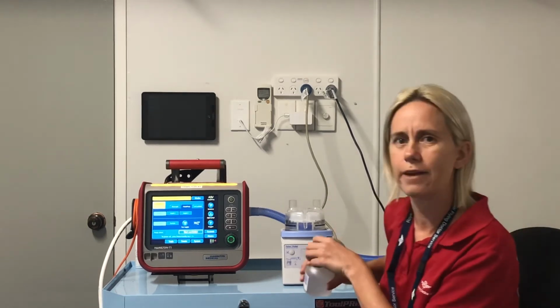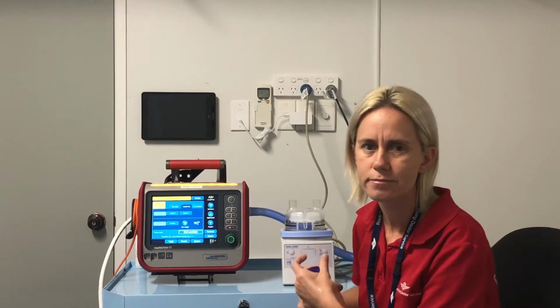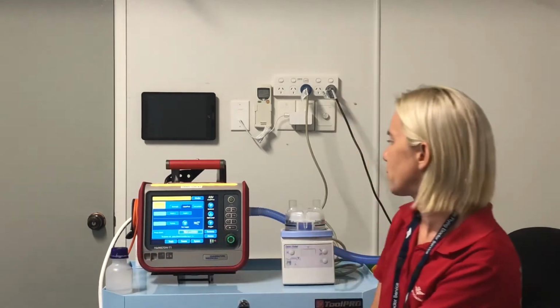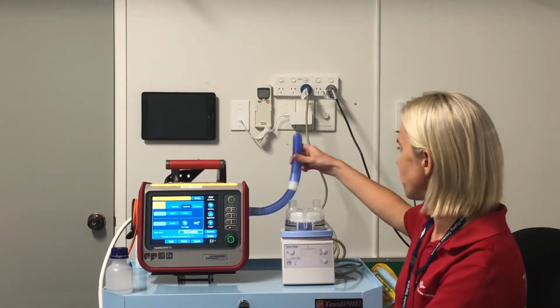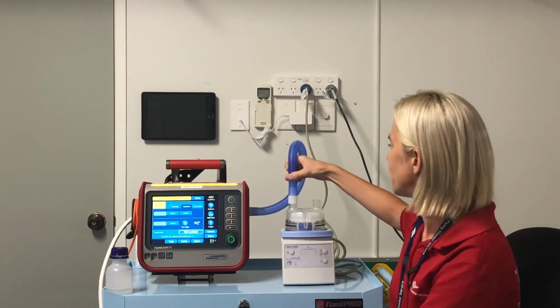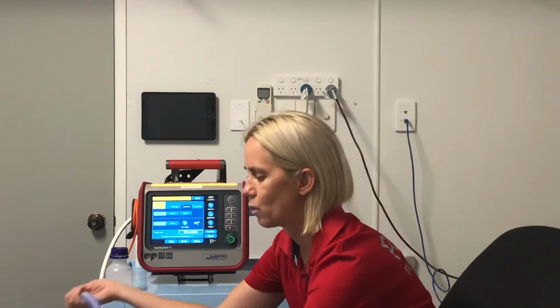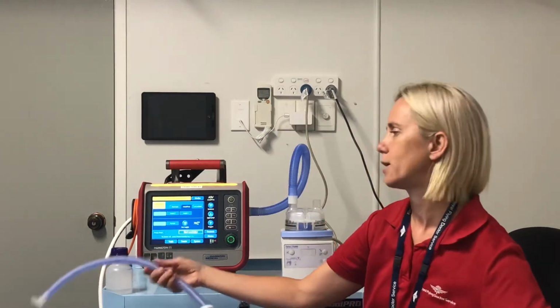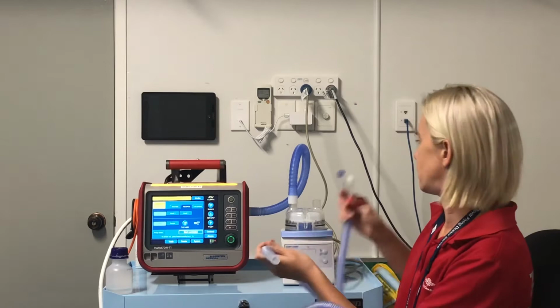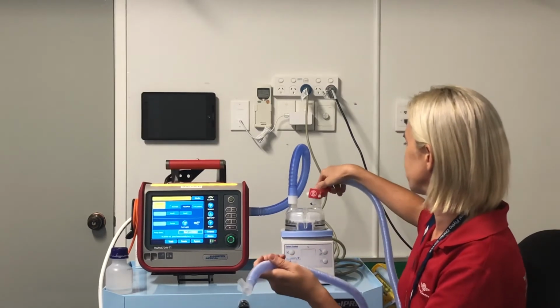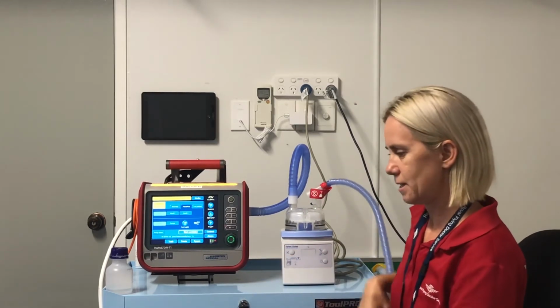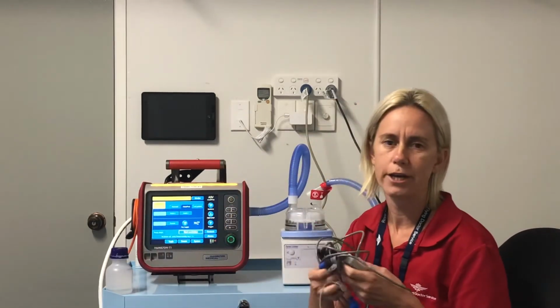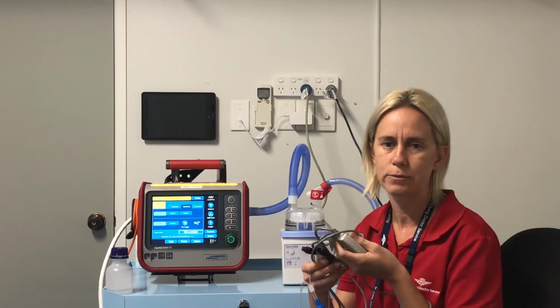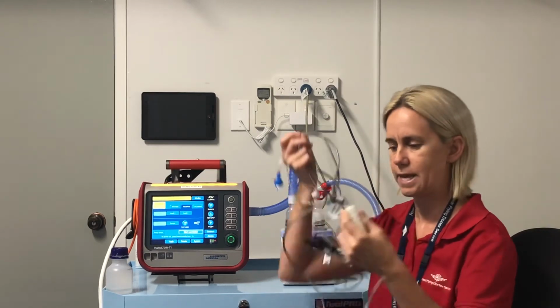And this is all in the high flow pack as well. Since we've done the pre-op test earlier today, we'll connect the dry line to one side of the chamber, and then to the other side of the chamber is where you connect the patient line. So that just clips on there. Perfect. In the high flow pack, we have the blue line, which is the temperature probe, as well as the yellow line, which is the heater probe.